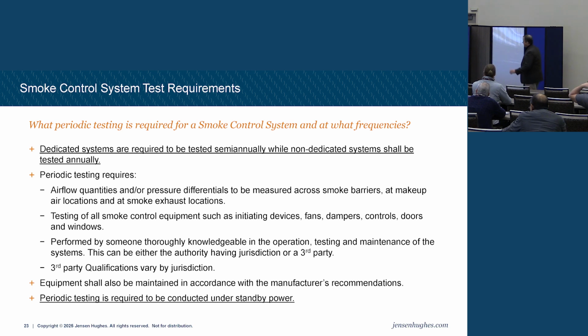Okay, I hate slides with a whole lot of text on them, so I'll try to paraphrase this for you. What is periodic testing? What periodic testing is required for smoke control systems, and what is the frequency? We talked a lot about that, right? Dedicated versus non-dedicated. Non-dedicated systems shall be tested annually, and the periodic testing requirements are airflow quantities and pressure differentials.